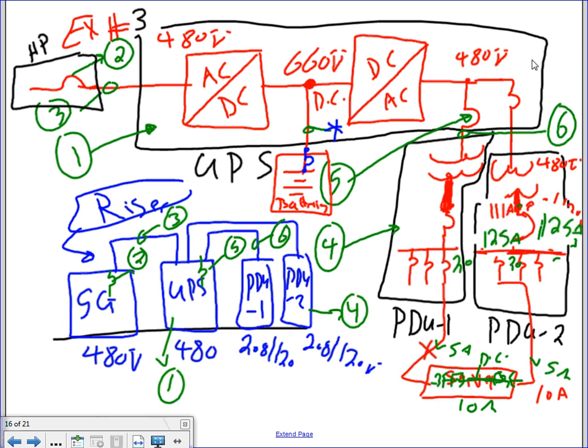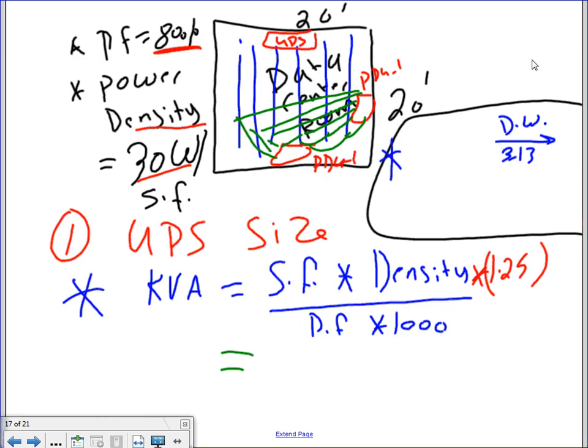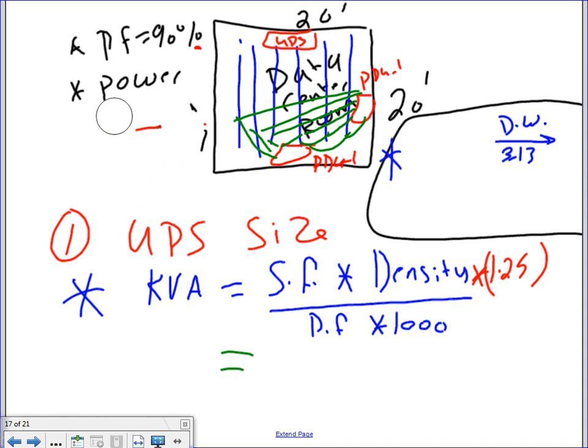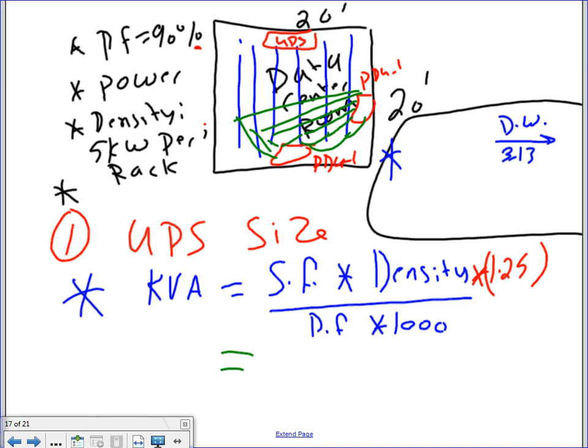The same pictures, everything continues to be the same. But this time, I'm going to size it based on the following. I would like you guys to change this one to 0.9, please. I have a 90% power factor. Instead of the density we used before, we're going to use the density here. If you change this one, we're going to have 5 kW per rack, and I have 24 racks. The same room, guys, 24 racks, same room.